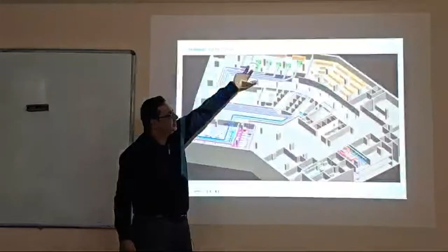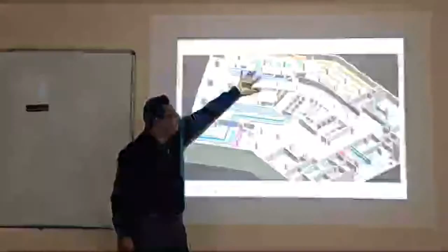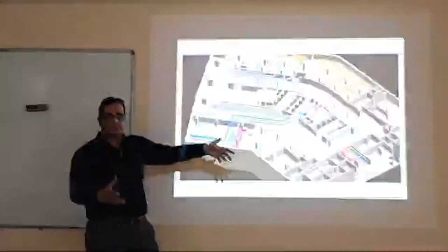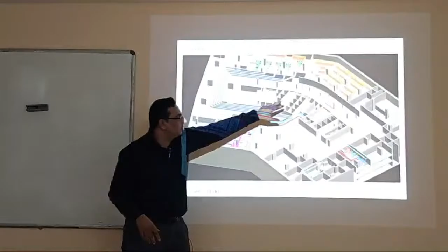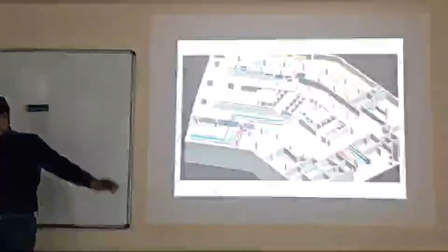So defining the height of a basement is subjective to how the services are reaching into the core. If you see the air conditioning plant room here, we have the DG sets, the LT panel, electrical panels. The DG set will come with the flue pipe, which I spoke about regarding stack issues. The flue pipe will come to the core, and within the core it starts reaching to the building top, and that's how it will start looking in the picture.